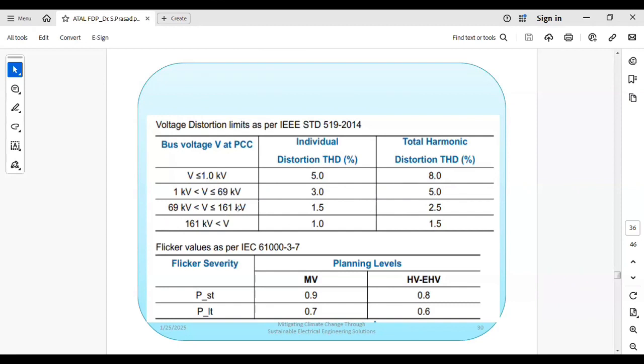Similarly, for 69 kV to 161 kV, and if the voltage rating at the POI is more than 161 kV, then individual harmonics have to be less than 1%, and the total harmonic distortion at the point of interconnection has to be 1.5%. Similarly, flicker is nothing but voltage fluctuations, and it is specified in terms of long term and short term flicker severity.